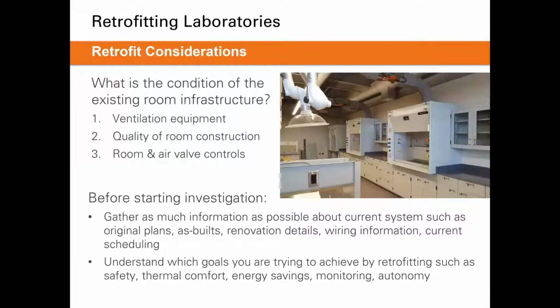I've broken it down into 3 main areas. First would be ventilation equipment, so things in the room such as the fume hoods, snorkels, and the fans that serve the lab as well. Next would be the quality of the room construction, so windows, doors, ceilings, any entry point into the room if there's a chance for leakage. And then the room and air valve control, so the valves controlling the hoods, the controllers that are controlling the valves, and then the controllers that determine the sequencing for the entire lab as well. So when I talk about controls, that's all those things.